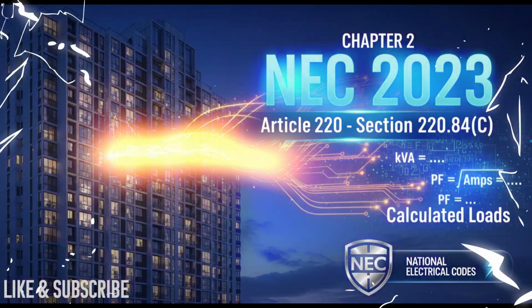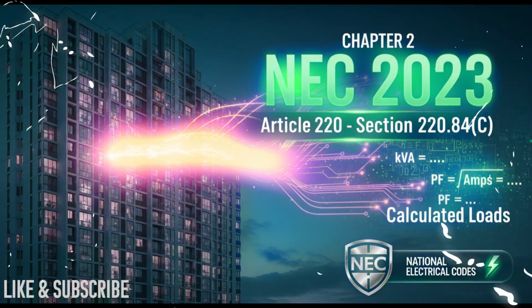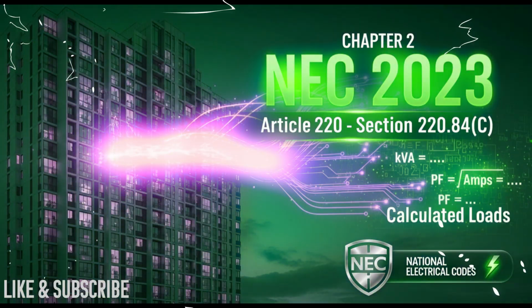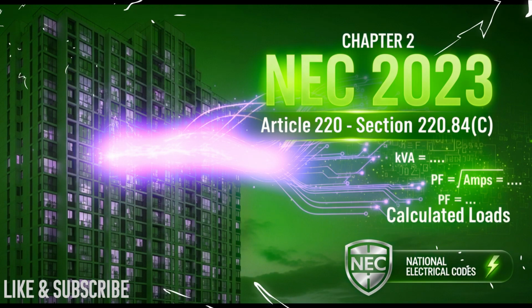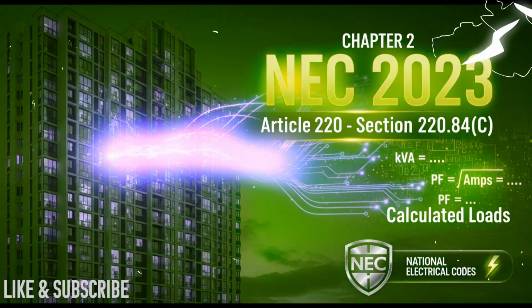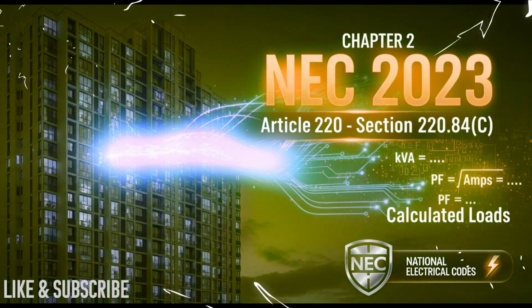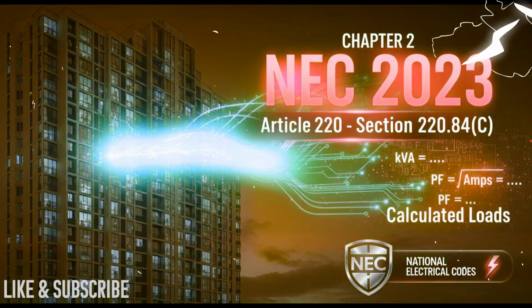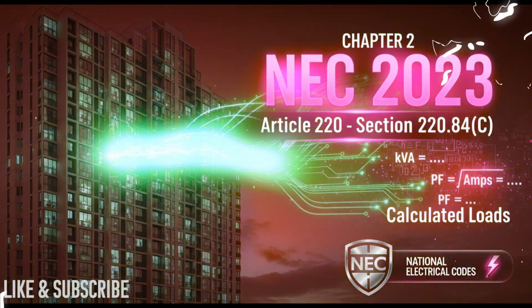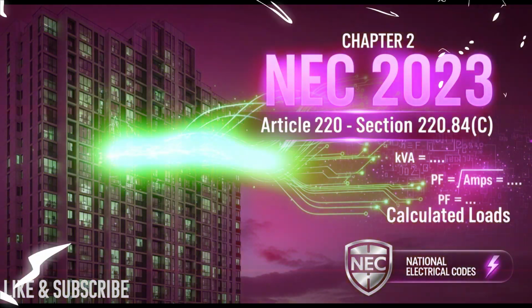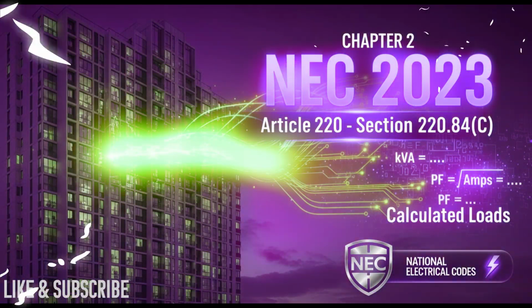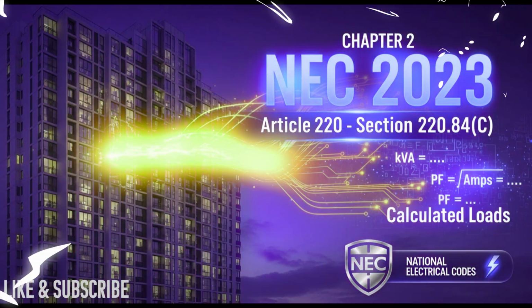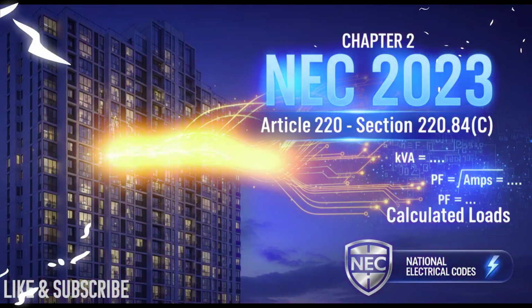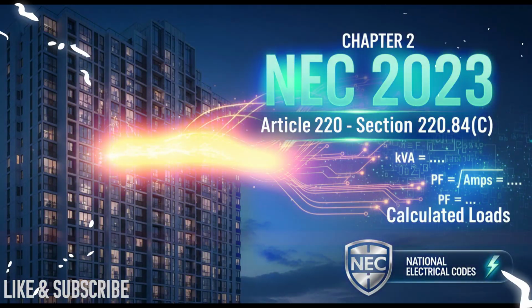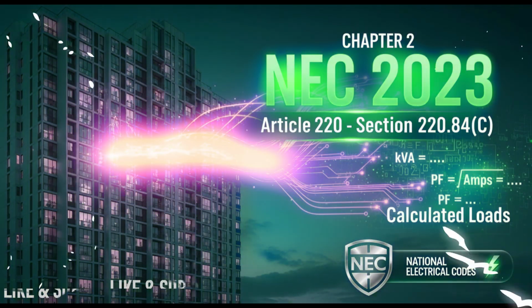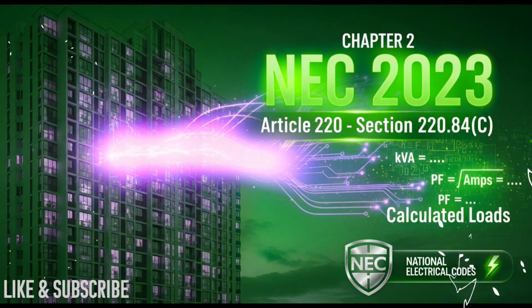And that brings us right to the mathematical heart of this deep dive, section 220.84. That's the one dealing specifically with multifamily dwelling calculated loads. All right, section 220.84. So what's the core idea behind this specific calculation? Well, the main purpose is to establish the full required electrical load. Think of it as the absolute maximum theoretical demand, before the designer is allowed to apply what we call demand factors. See, the code isn't naive. It knows that in, say, a 100-unit building, not everyone is going to run their AC, their oven, and their washing machine all at the exact same peak moment. Right, that makes sense. That's the efficiency part you mentioned. Yeah, that comes later. They use these efficiency factors, often from tables like 220.84(B), to safely and realistically reduce the final service size. It makes it more economical. But first, you have to calculate the total load, almost as if every single light could be on, every appliance could be running flat out.